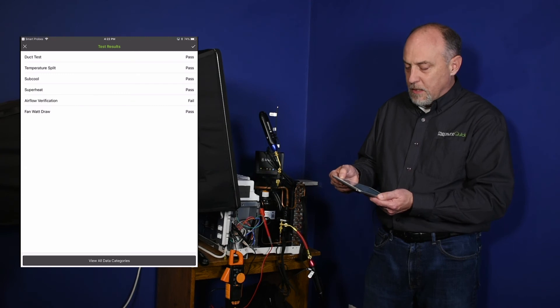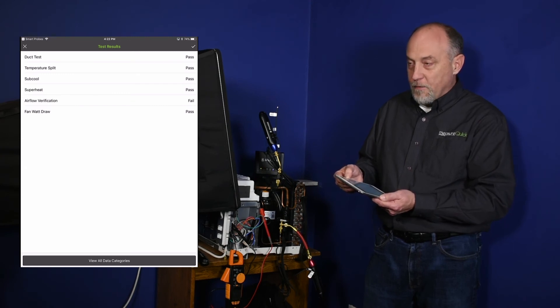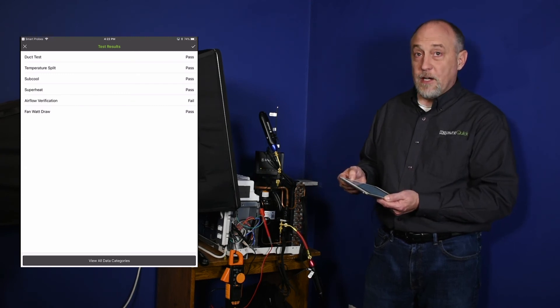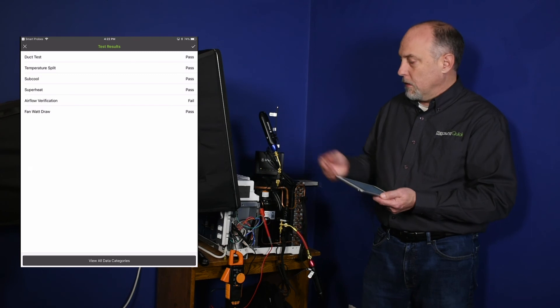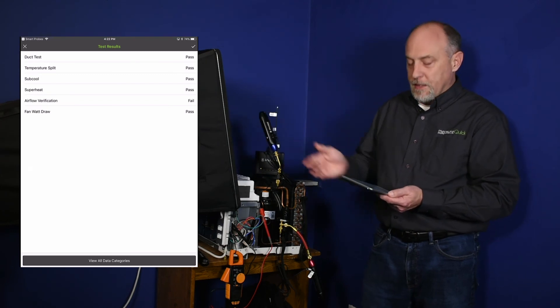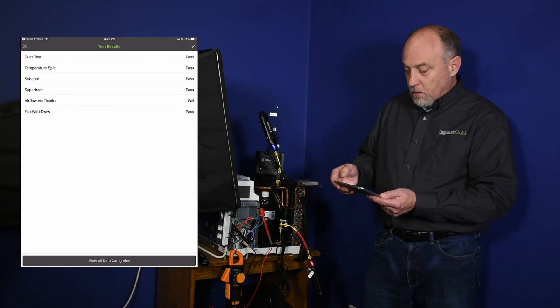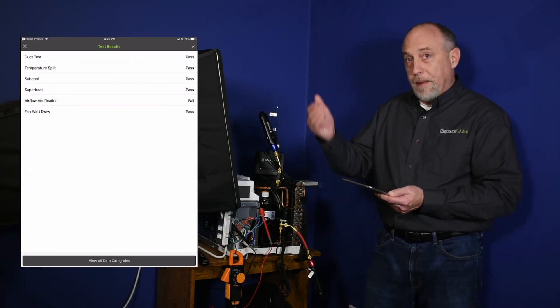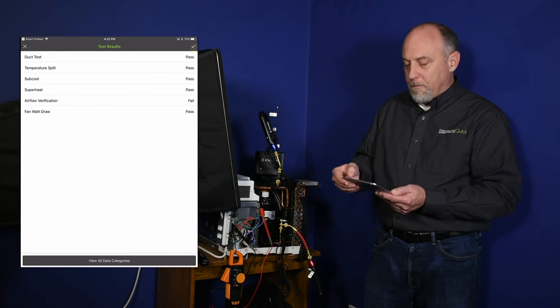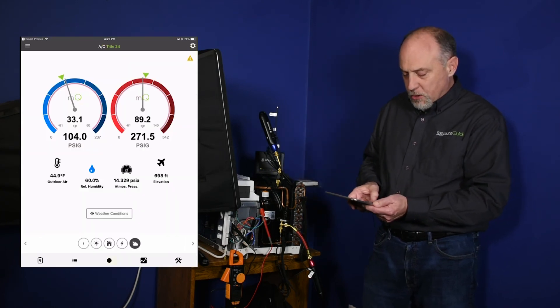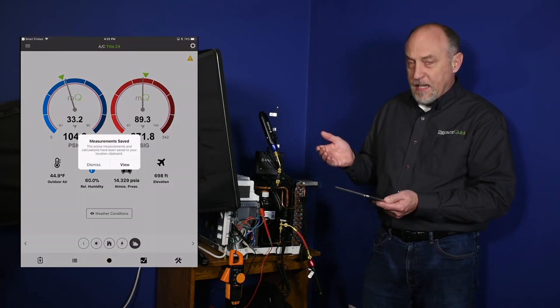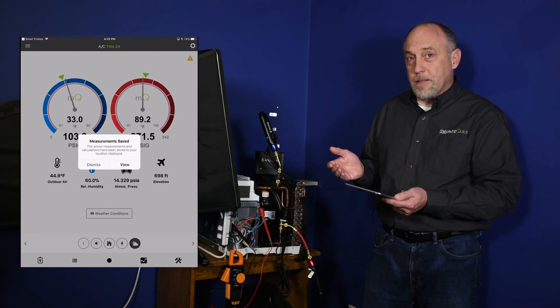I'm going to look at my test results and you can see that my duct test passed, my temperature split passed, my subcool passed, my superheat passed. My airflow verification failed because, hmm, the capture hood is wide open at the top here, it doesn't surprise me. So now we know pass, fail automatically. Again, super easy, super to do, fast to do. I'm going to hit the record button at the bottom. That's going to allow me to view the report.